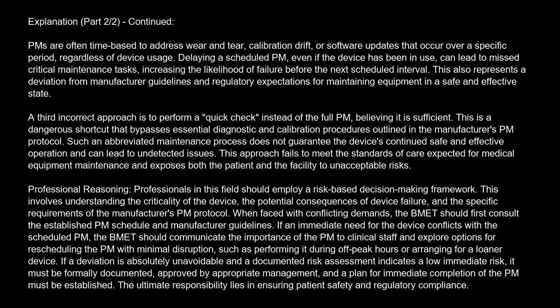Professional reasoning. Professionals in this field should employ a risk-based decision-making framework. This involves understanding the criticality of the device, the potential consequences of device failure, and the specific requirements of the manufacturer's PM protocol. When faced with conflicting demands, the BMET should first consult the established PM schedule and manufacturer guidelines. If an immediate need for the device conflicts with the scheduled PM, the BMET should communicate the importance of the PM to clinical staff and explore options for rescheduling the PM with minimal disruption, such as performing it during off-peak hours or arranging for a loaner device.